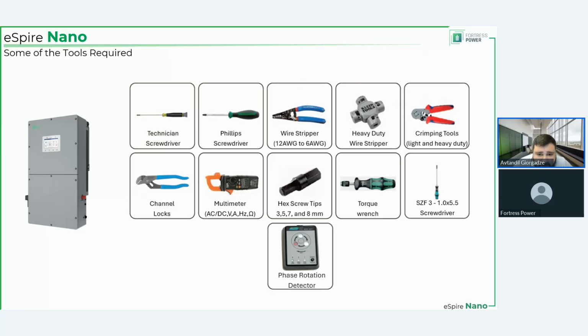It must be clockwise. And a phase rotation detector allows you to determine whether or not it's clockwise the way it connects to the inverter. So L1 to L2 to L3, that should be clockwise rotation, and that's how it should be connected to the grid side of the inverter. And the same applies if you're connecting a generator or AC coupled PV. Although I do believe AC coupled PV automatically adjusts, but don't quote me on that. In any sense, you need to use a phase rotation detector. This is a must, and it's not that expensive.